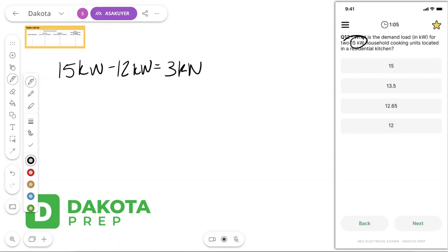We're over 12 by 3 kW, which means we have to increase that 5% 3 times, right? So that would be 5, 10, 15%. We need to increase that column C number by 15%, okay? Another way to look at that, you could say, well, I'm over by 3 kW times 5%, which would be 0.05, would give us 0.15 or 15%.